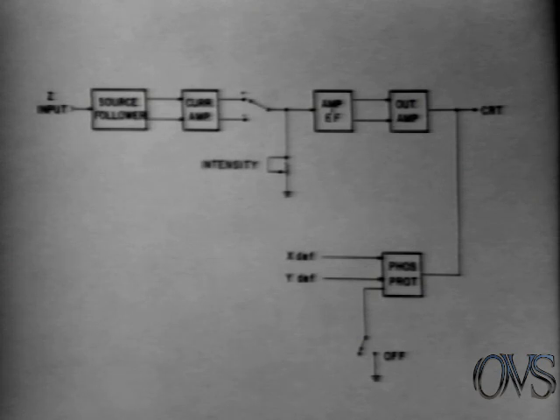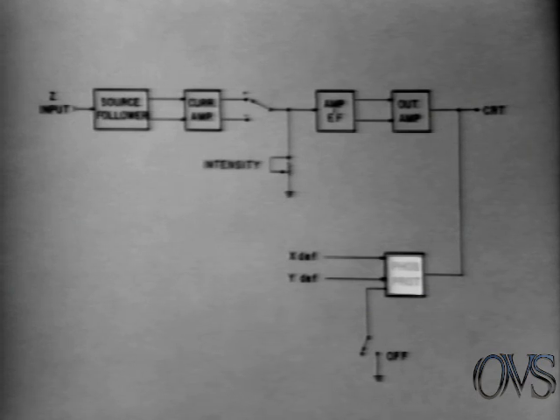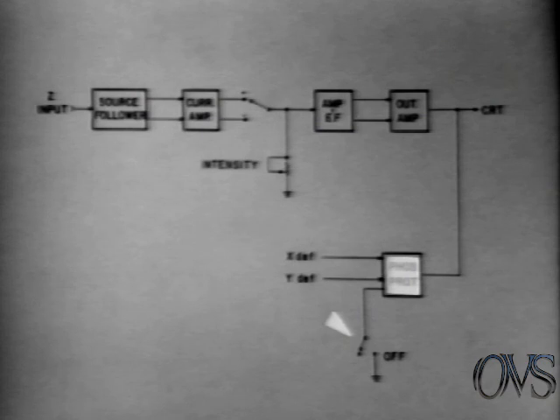The phosphor protection circuit protects the CRT from burns that could be caused by a stationary or slow-moving beam. It does this by limiting the output of the Z-axis amplifier. In most applications, this switch should always be in the on position. Let's try this one. A malfunction has occurred, and we have no X-axis deflection. What can we do to further isolate the problem?